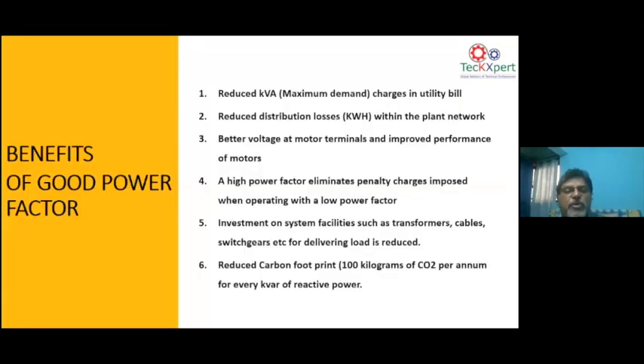As you all know, improving power factor has many benefits. It reduces the kVA demand on the transformer or on the grid, and even for a consumer who is billed on a kVA basis, there is a kVA reduction, so there is a possibility of reducing the electricity bill. Similarly, the kilowatt hour losses in the grid also reduce substantially, because when you have a low power factor, naturally a lot of reactive energy is flowing through the transformer to the load. That reactive current also adds to the I squared R losses, so it increases the kilowatt hour losses.